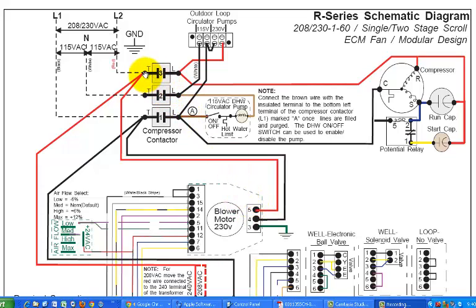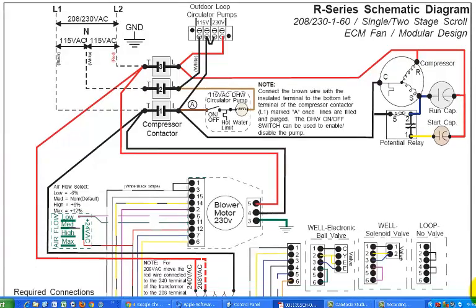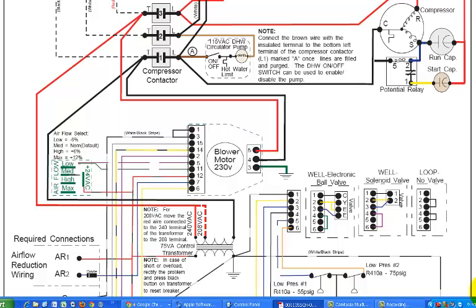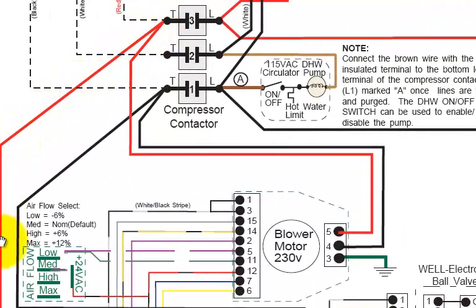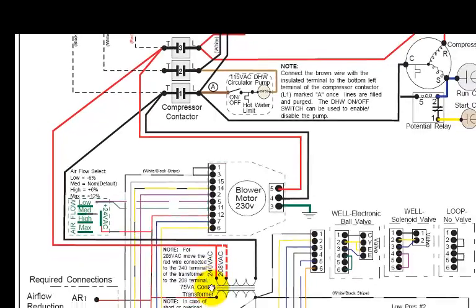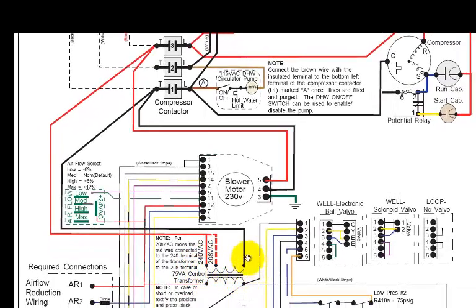Also, leading off those L1 and L2 terminals, we've got lines coming over to a very, very important component, that being the transformer. And so I'm going to scroll this down just a little bit so we can follow that a little bit more completely. And so again, you'll notice that off that L2 terminal, we've got the red wire coming over, and it is feeding, in this particular case anyway, the left-hand side of this transformer. And also coming off the L1 terminal, the black wire is coming over and feeding the other side of the transformer. And, is it critical that the red be the left and the black be the right? No. All that's critical is that we have a potential difference between the 2 terminals on the transformer of something in that region of the 240 volts. So these lines then are feeding 240 volts to what we call the primary side of that transformer.